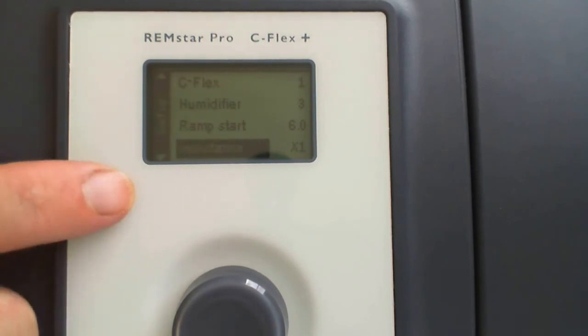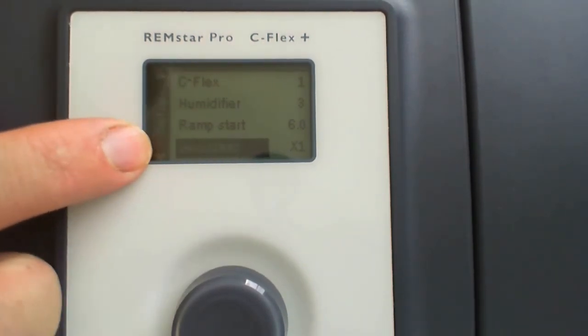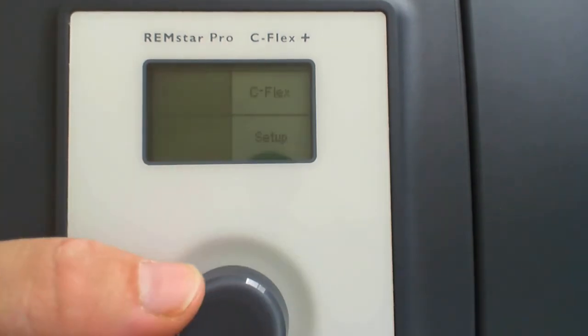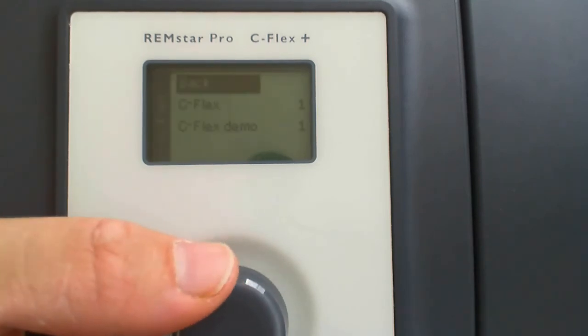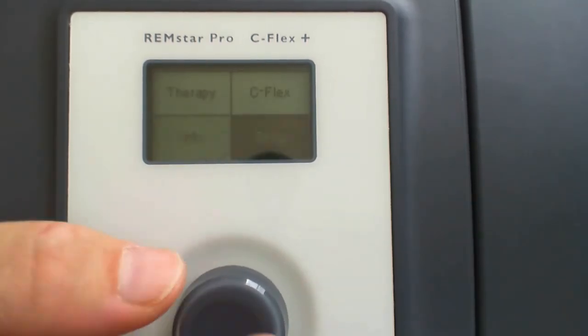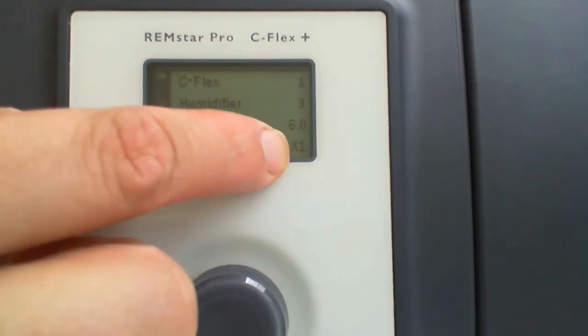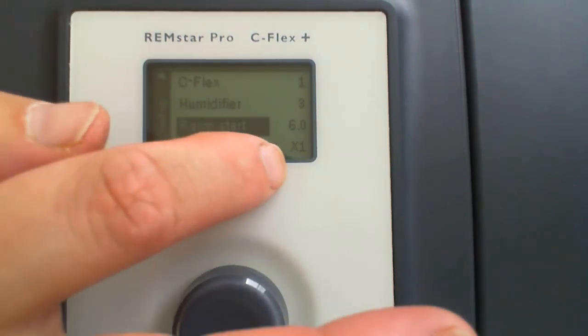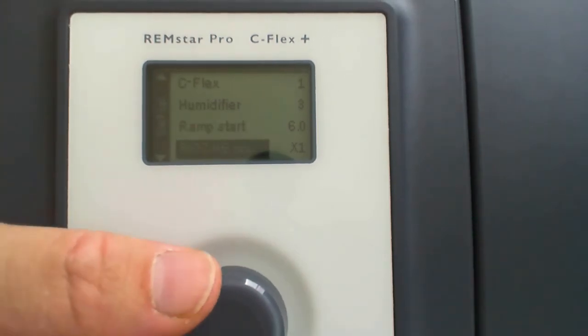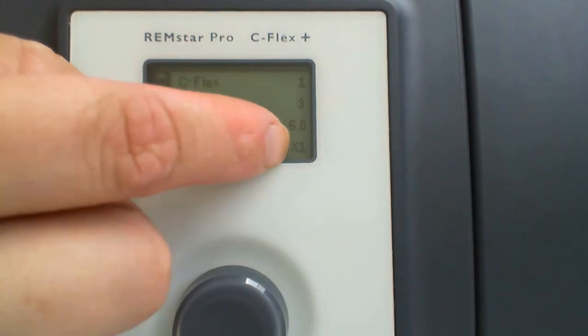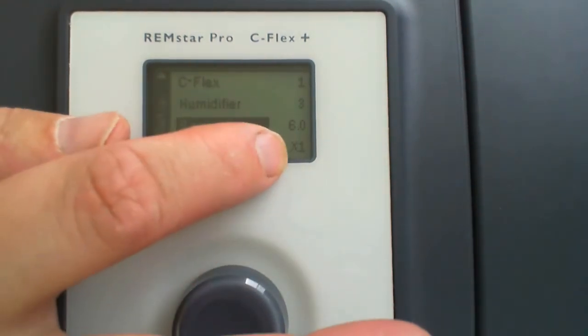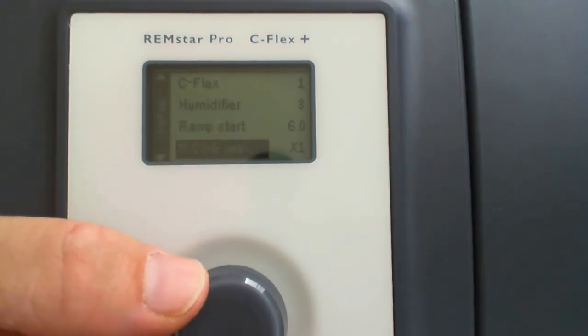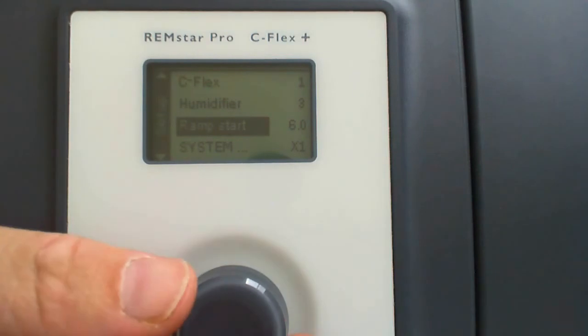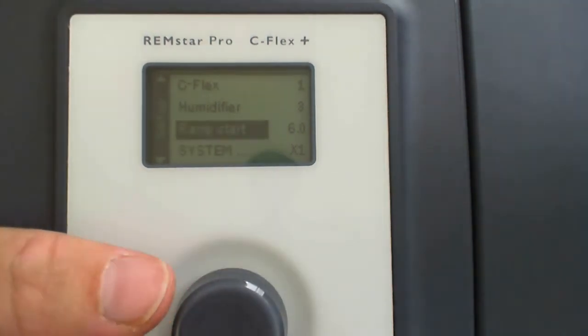And let's get the focus back. So here's another area. If this is enabled, what this says is System 1 resistance. With System 1 resistance, if you have different CPAP masks, those come with a rating, and it'll be 1x through 5x, about what your System 1 resistance setting should be. Now, this is another feature, and it's not necessarily a comfort feature, but if you're going to be using different CPAP masks, if you have a full face, a nasal mask, a nasal pillow, and you're going to bounce between them, this setting is going to allow you to get the same therapy, irrespective of what mask you're using.